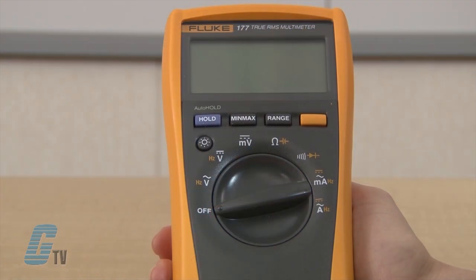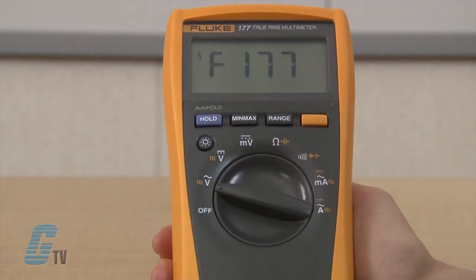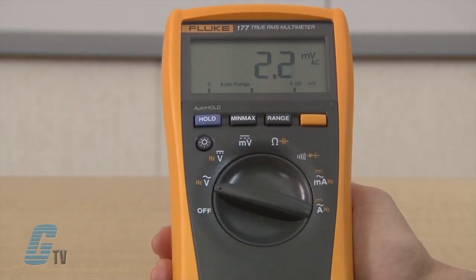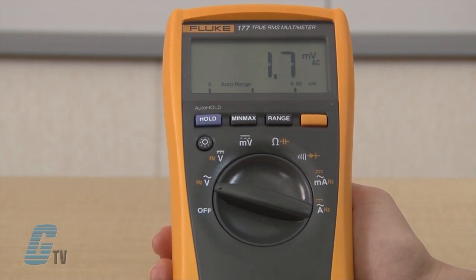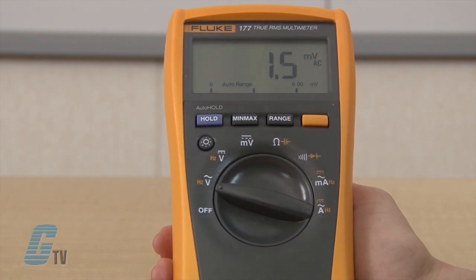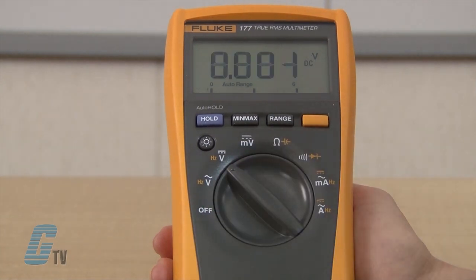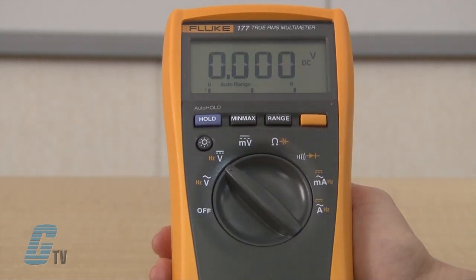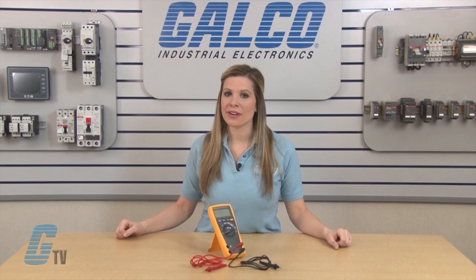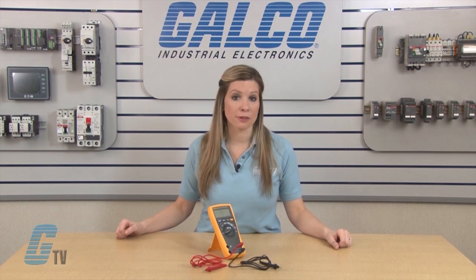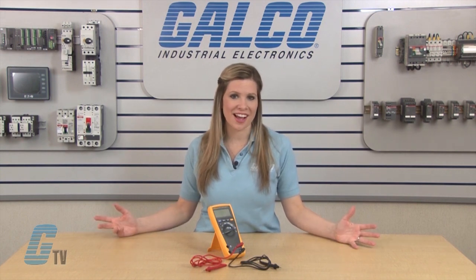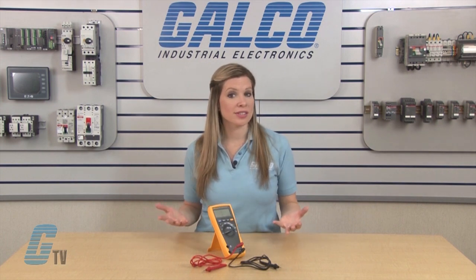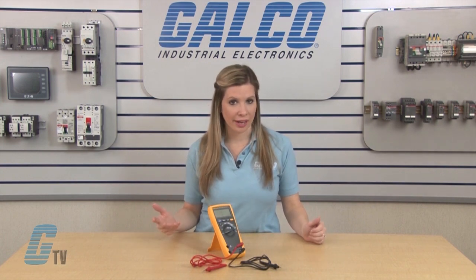First, I will show voltage measurements by going to the V symbol. There may be two of them, one for AC and one for DC. The symbol with one solid line and a dotted line parallel to it is for DC voltage, and the V with the wave over it is for AC voltage. Some meters may have an MV setting to check for millivolts, and some may have numbers to define a specific range for testing. These ranges can be adjusted to allow a more accurate reading.